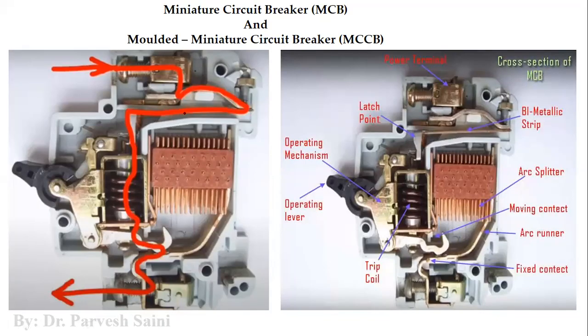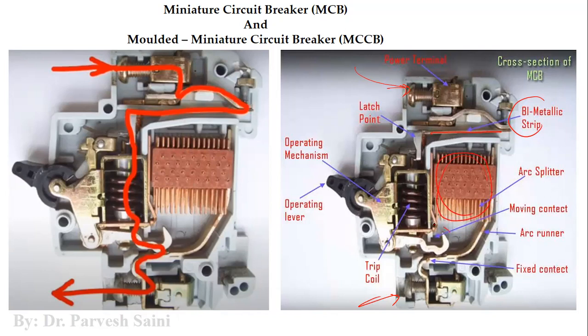MCBs are installed at home at the distribution point. Inside an MCB we have power terminals where the main supply is connected, terminals where the load is connected, a bimetallic strip, a coil which when energized breaks the circuit, a moving contact, and an operating lever used to disconnect the circuit manually if needed.